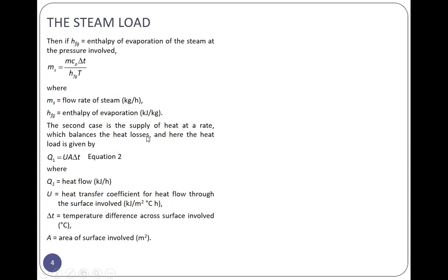The second case is the supply of heat at a rate which balances the heat losses. And here, the heat load is given by Q1 is equal to UA delta T, equation 2, where Q1 is the heat loss, U is the heat transfer coefficient for heat loss through the surface involved, kilojoule per meter squared C hour. Delta T is the temperature difference across surface involved, degree C. A is the area of surface involved, area of the wall of the tank.